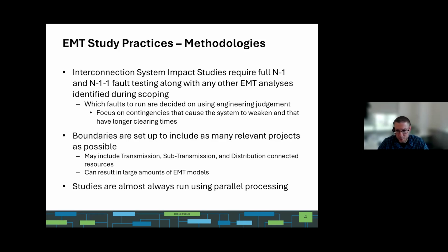As I mentioned, we set up these boundaries, cutting out a portion of the system since it's very difficult to run an extremely large part of the system. So we cut out certain portions and develop a boundary, equivalencing the outside network in order to capture the phenomena we're looking for, but also to make sure we can run it in a reasonable amount of time. EMT studies are notoriously computationally expensive, so it's very important to understand how large a system you're trying to model and run. That's why in pretty much every case we run these studies using parallel processing.